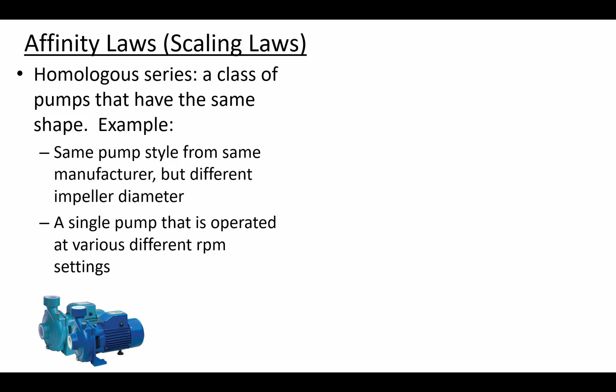You can think of it as pump number 1 and pump number 2. These related pumps have similar characteristics, and if you change one or two parameters, you can use these scaling laws to determine the updated performance curve for the pump.